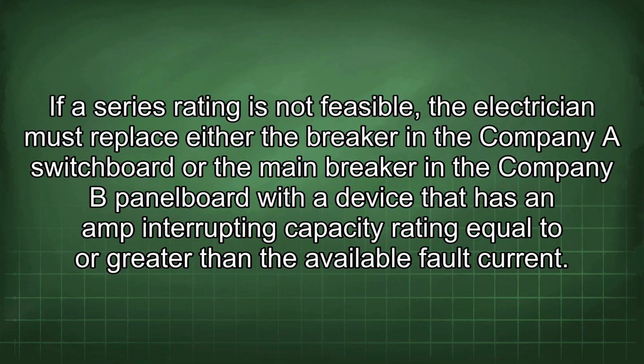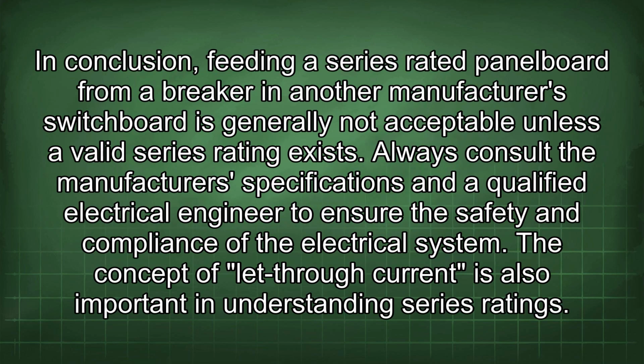If a series rating is not feasible, the electrician must replace either the breaker in the Company A switchboard or the main breaker in the Company B panelboard with a device that has an amp interrupting capacity rating equal to or greater than the available fault current. In conclusion, feeding a series-rated panelboard from a breaker in another manufacturer's switchboard is generally not acceptable unless a valid series rating exists. Always consult the manufacturer's specifications and a qualified electrical engineer to ensure the safety and compliance of the electrical system.